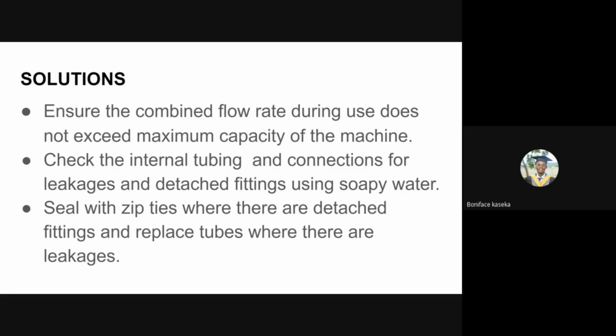It is recommended that when you are using an oxygen concentrator, and let's say you want 8 liters per minute, and you have an oxygen concentrator which has 10 liters per minute, you add at least 1 liter per minute to the combined flow rate of the oxygen flow splitter. So if you have an 8 liters per minute combined flow rate, you set your oxygen concentrator at 9 liters per minute, so that the extra 1 liter per minute can compensate for the losses that happen due to the length of the tubing and other losses.